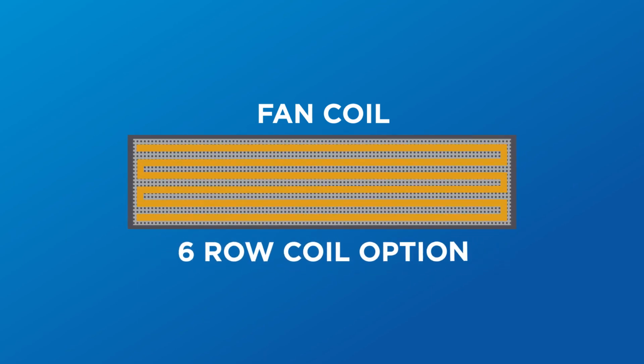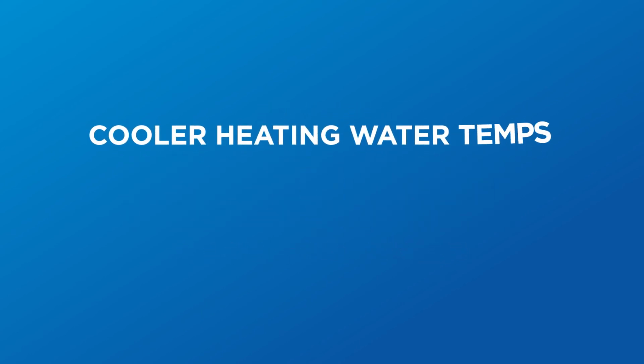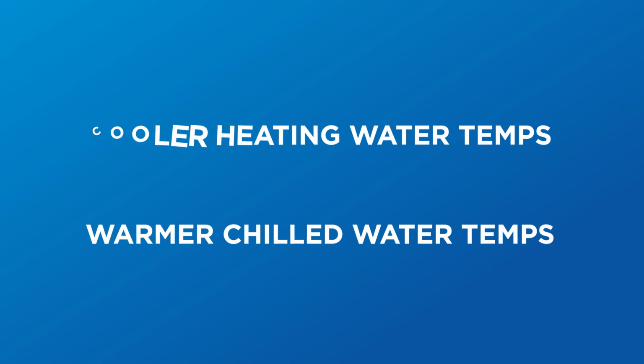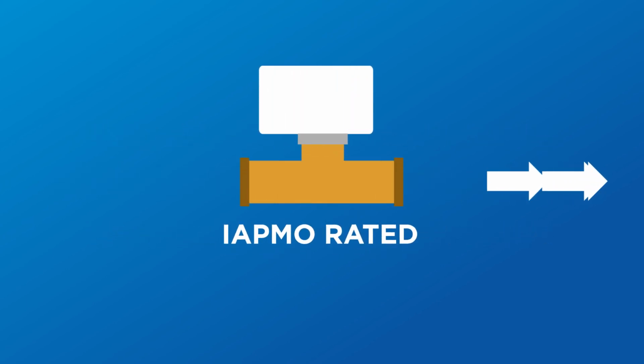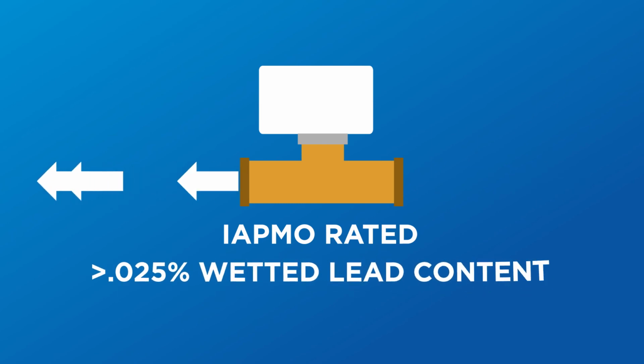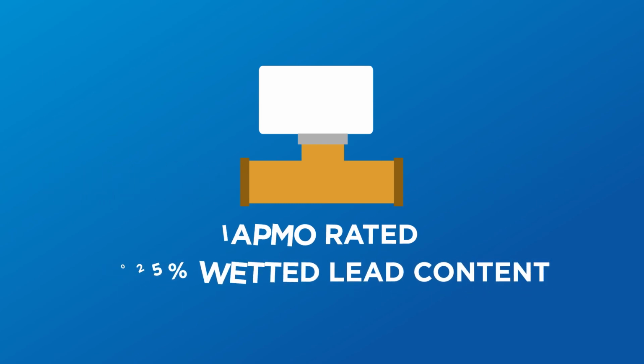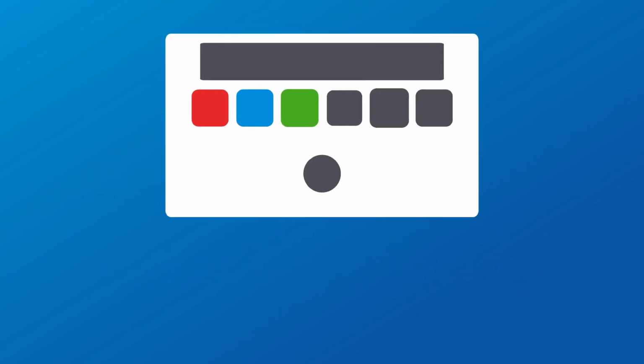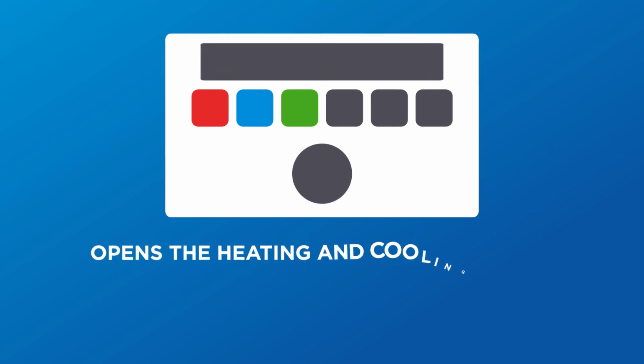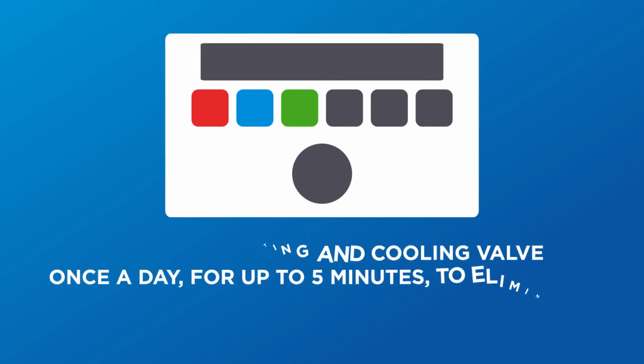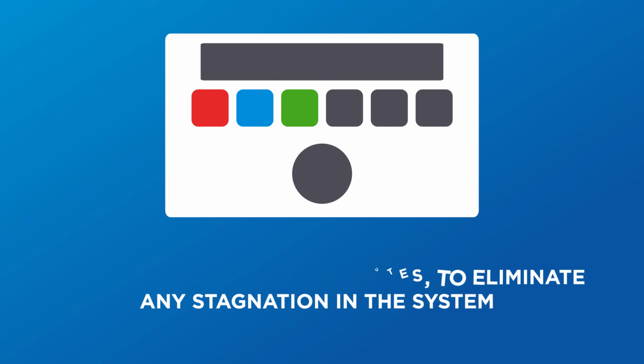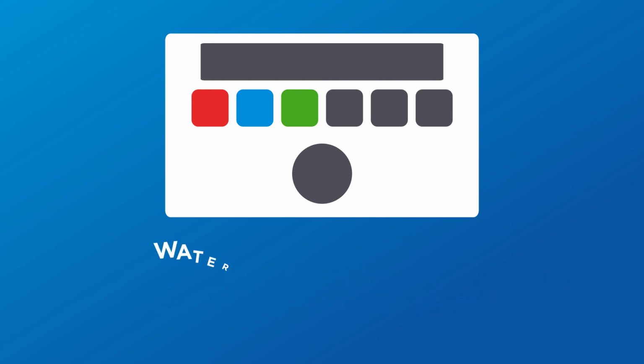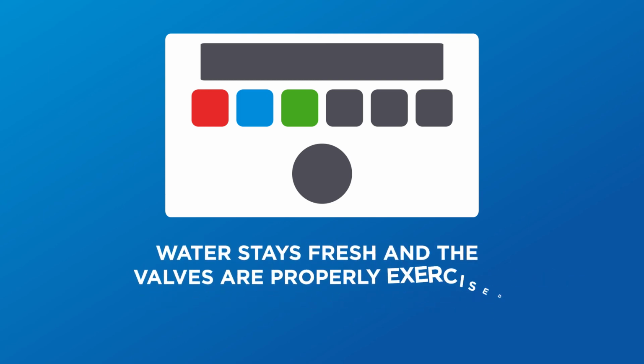Utilizing a 6-row coil option with circuiting allows us to use cooler heating water temps and warmer chilled water temps. We factory mount 2-way valves, which are IAPMO rated for less than 0.025% wetted lead content for potability, and each terminal unit has a control board that opens the heating and cooling valve once a day for up to 5 minutes to eliminate any stagnation in the system, ensuring the water stays fresh and the valves are properly exercised.